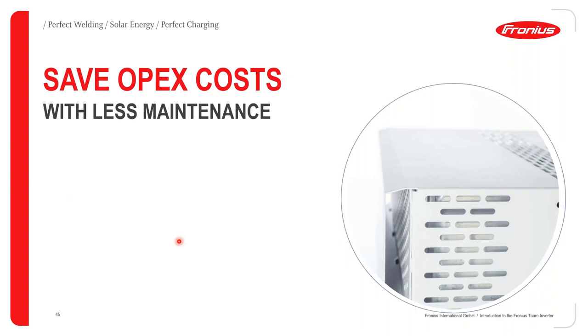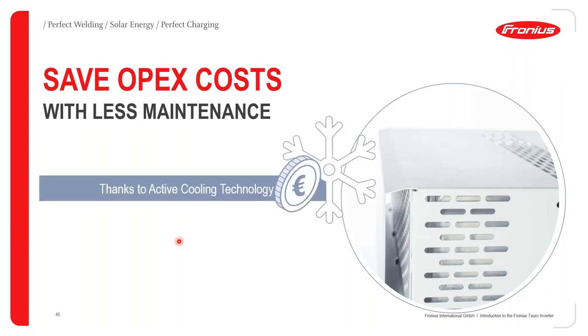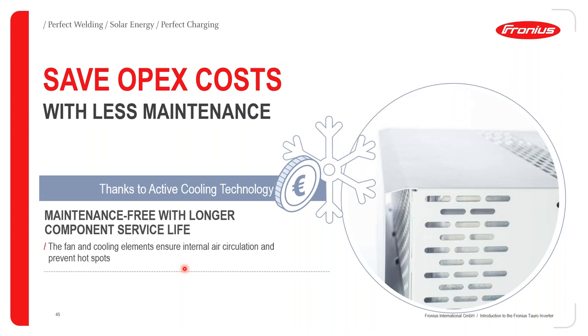And then with that also comes less maintenance. With the low frequency of visits to sites by the site engineer or technician, this of course leads to lower operating costs. It is of course thanks to the active cooling technology implemented in the Tauro, because it ensures maintenance-free operation of the inverter, and of course longer component service life. The fan and cooling elements in the inverter ensure internal air circulation, and of course prevent hot spots. And once hot spots are prevented, especially in the case of power electronics, it ensures that your device, in this case the Tauro, functions optimally. So this of course means that there will be no need for any prescribed maintenance intervals by the specialist.